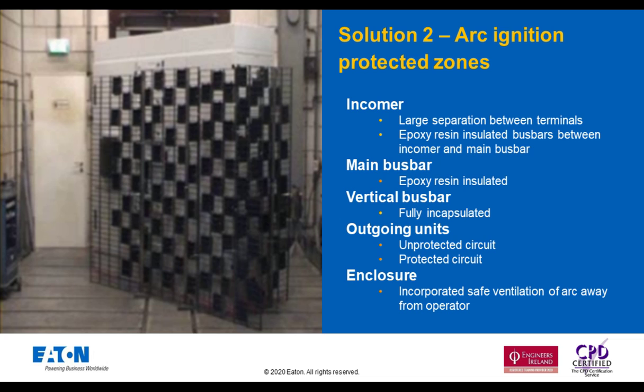So, for instance, on the incomer of the switchboard, you increase the separation distances between the terminals. Potentially you can use epoxy resin insulated bus bars between the incomer and the main bus bar. On the main bus bar itself, you can apply an epoxy resin insulation. Likewise, on the vertical bus bars, you can fully encapsulate them. These methods prevent a flashover between phases if a piece of wire or a tool was accidentally dropped on the bars, or some vermin got into the switchboard during service. And then there are things on outgoing units. You can have unprotected circuits or protected circuits.